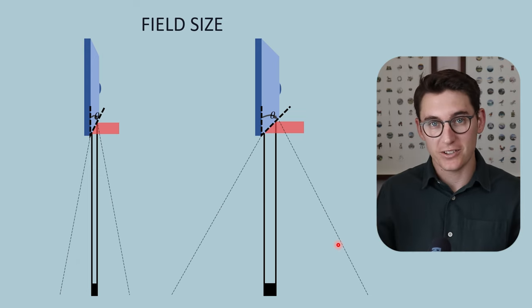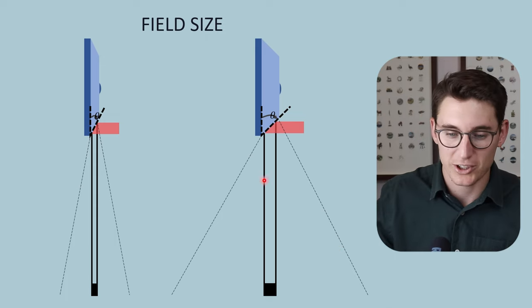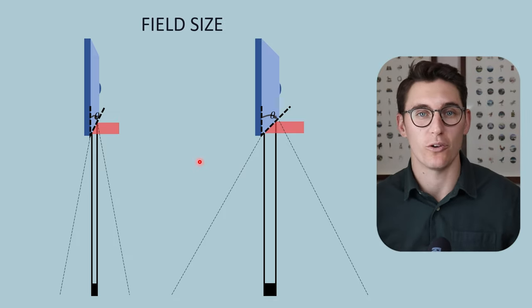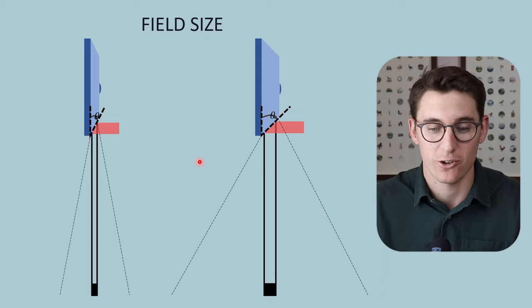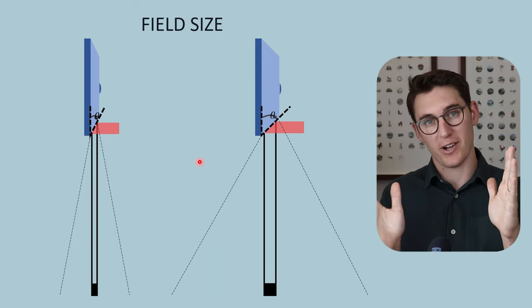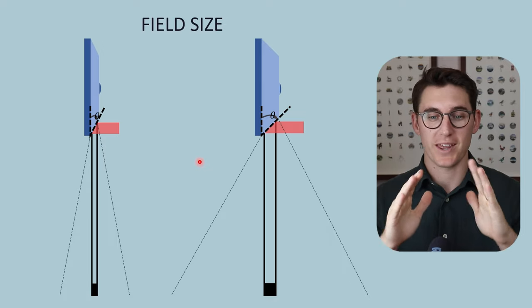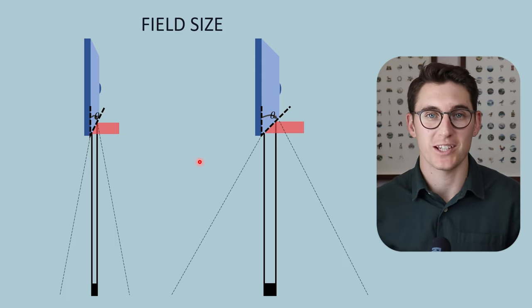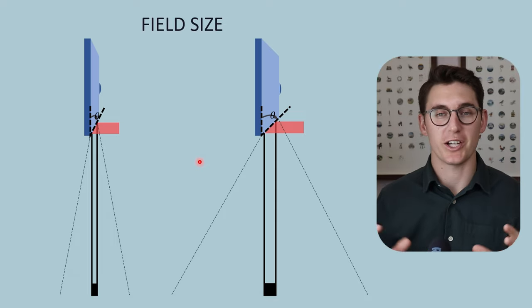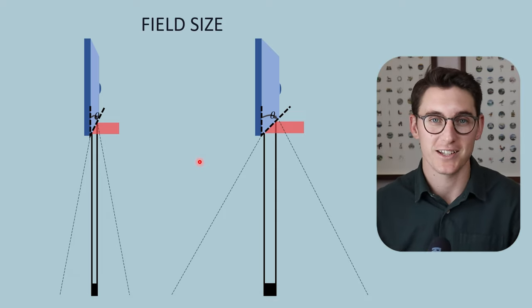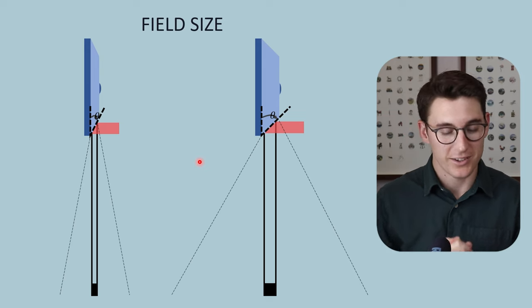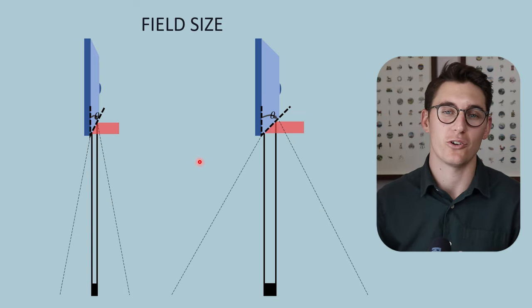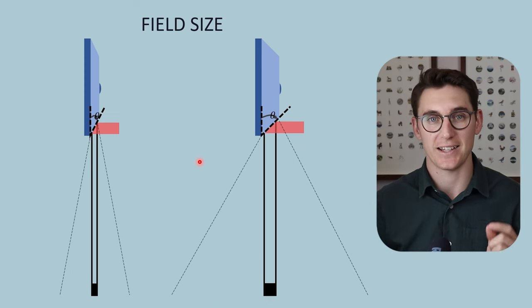It's a trade-off between field size and effective focal spot. Additionally, increasing the anode angle increases the actual focal spot, allowing the anode to tolerate heat better — another reason to use a larger anode angle. So the two major things that change with anode angle are the effective focal spot width and field size. This is also a common exam question. Beyond these two effects, changing anode angle also produces a phenomenon known as the anode heel effect, which we'll look at in our next lecture.